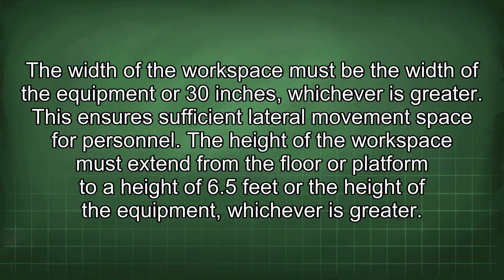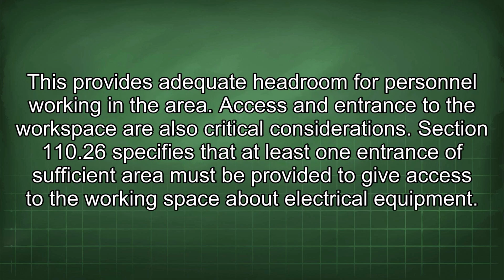The width of the workspace must be the width of the equipment, or 30 inches, whichever is greater. This ensures sufficient lateral movement space for personnel. The height of the workspace must extend from the floor or platform to a height of 6.5 feet or the height of the equipment, whichever is greater. This provides adequate headroom for personnel working in the area.